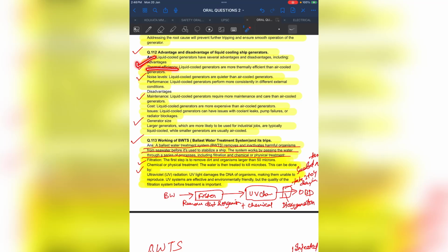What are the advantages? Thermal efficiency: liquid cooled generators are more thermally efficient than air cooled generators. Noise level: liquid cooled generators are quieter than air cooled, so the noise level is very low. Performance wise, liquid cooled generators perform more consistently in different external conditions, meaning that whatever the ambient temperature, they work consistently.